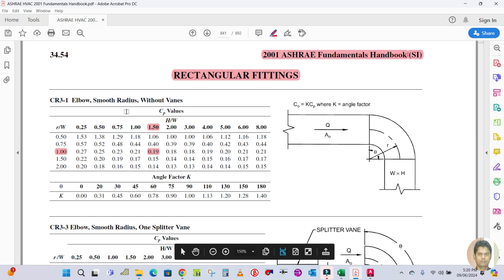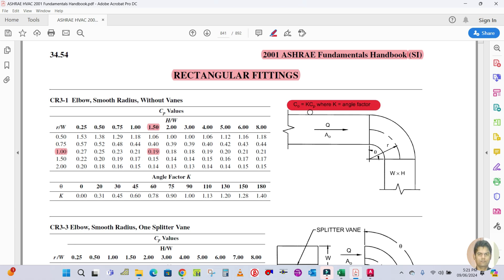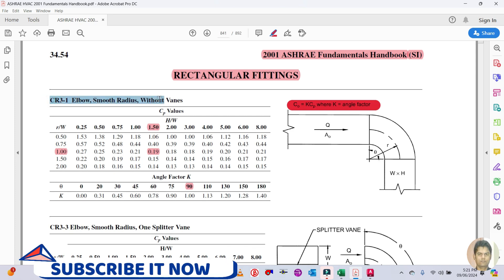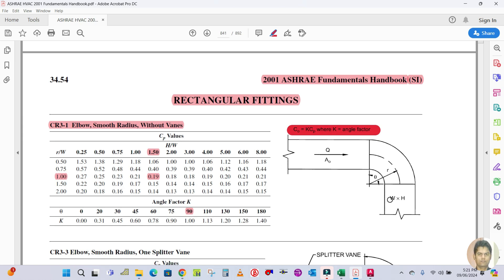How to get the Co value, and how to get the R/W, H/W, and Cp value. The loss coefficient Co equals k times Cp. To calculate Co, k is required and Cp is required. Cp is calculated from the table. K is the angle factor — for 45 degrees it is 0.6, and for 90 degrees it is 1.0. This is for the supply elbow, fitting name CR3-1: elbow smooth radius, rectangular fitting.